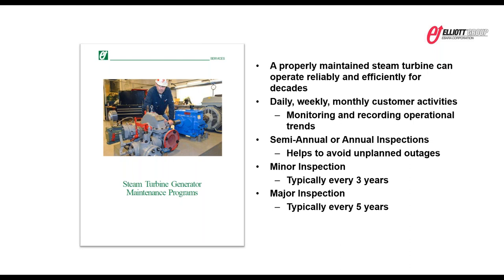The next level above an annual inspection would be a minor inspection. That's typically every 3 years. That's where we'll do all those visual inspections, just like with an annual, but now the unit's going to be shut down. We're going to open up the bearing caps and look at the bearings, checking for wear and tear on seals and bearings and things like that, and replace those parts if needed.